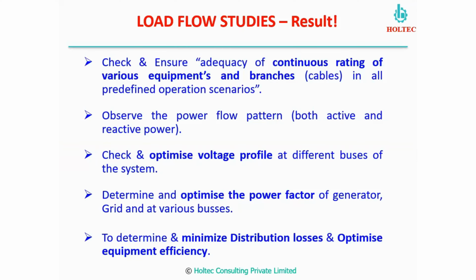Rather, generator has been used as a tool to maintain the unity power factor on grid, irrespective of the power factor which we are maintaining on the generator, except not less than 0.8, which is the rated one. Okay, but if you operate the generator with 0.8 power factor, and if you operate the generator with 0.95 power factor, there will be a substantial decrease in the load losses in the generator itself. And the generator load losses is approximately 35 to 40% of the total losses which is happening in the generator. So you can understand, if it is 96% efficiency of the generator, the amount of losses which you can save, you can very well calculate.